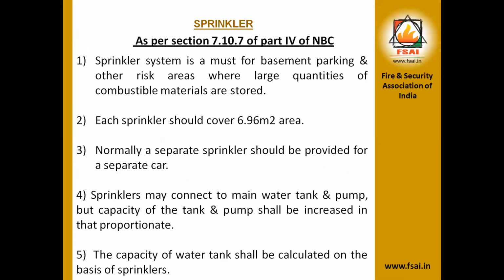Sprinkler system is for basement parking and other risk areas where a large quantity of combustible materials is stored. So we have to understand the threat and provide the sprinklers in that area. Each sprinkler should cover 6.96 square meter area. What this means is, the total area of the room divided by 6.96 is the number of sprinklers to be provided in a particular area.